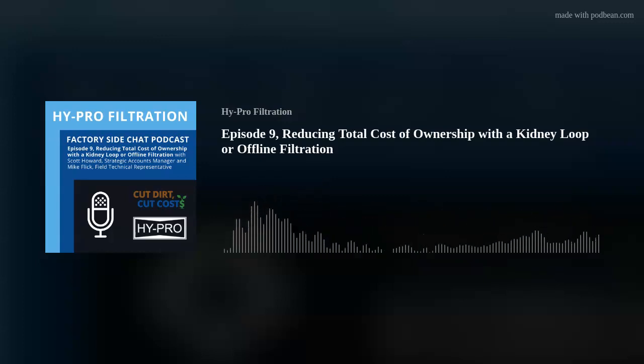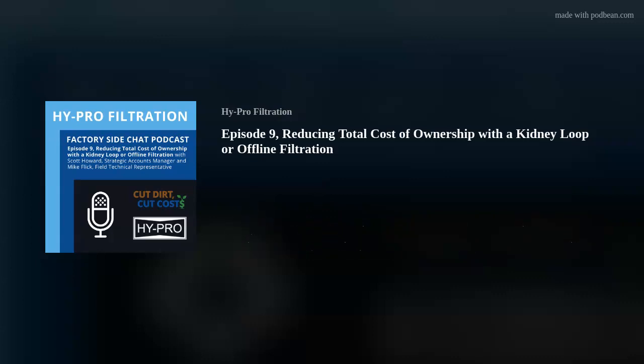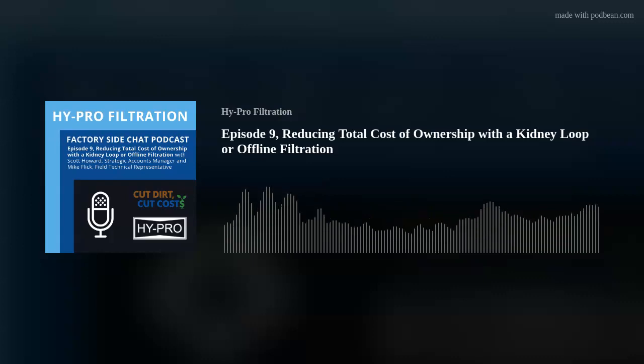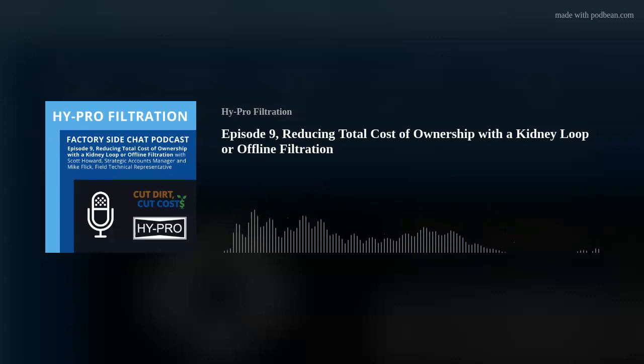So in sizing this kidney loop or offline filter unit, we look at the reservoir size. And then, like you mentioned, we also look at the environmental conditions. Is it in a clean room or is it in a very dirty, windy outside environment?